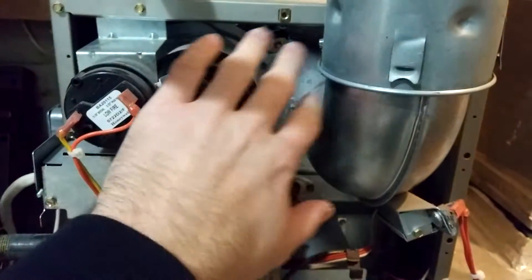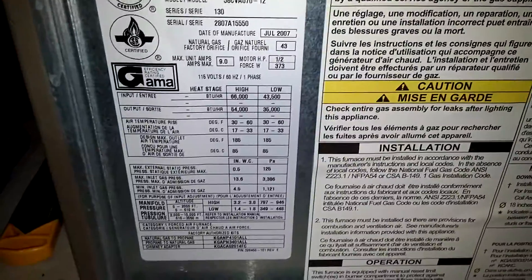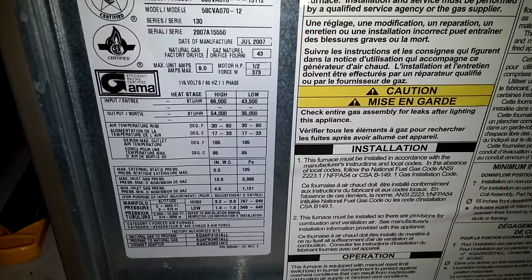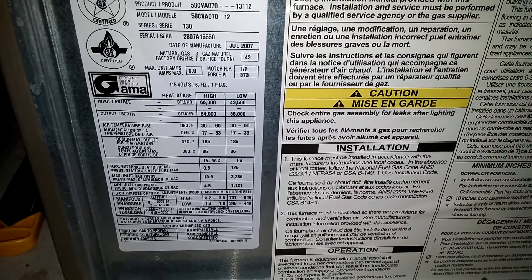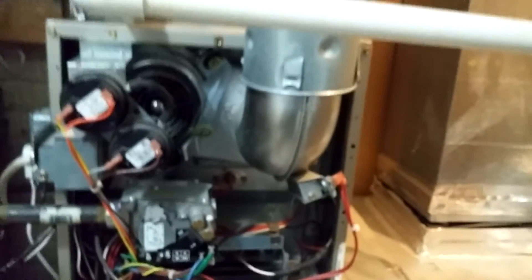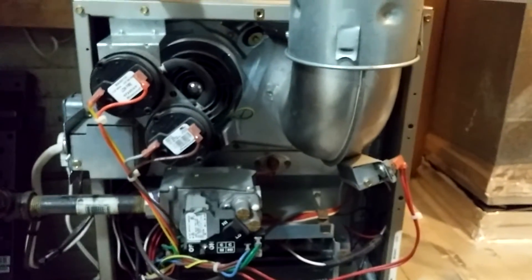It's got a two-stage gas valve, high and low pressure switches, your inducer back here, and it's got three burners. Three burners — hot surface ignition and your flame rod slash sensor back in there. In high stage it's 66,000 BTUs, outputs about 54,000. Low stage is 43,500, outputs about 36,000. I ran it fine all last winter with no issues.